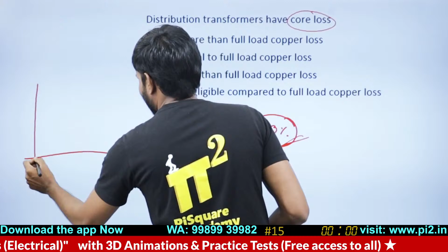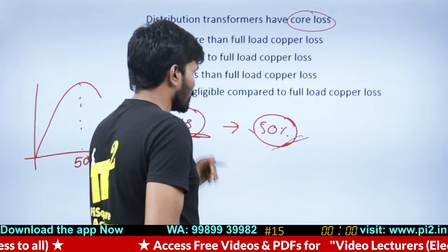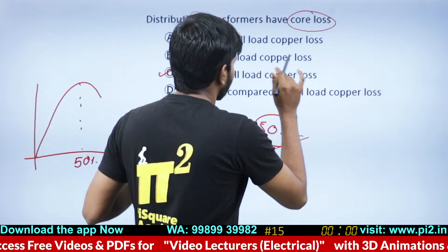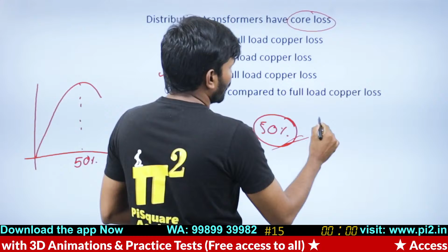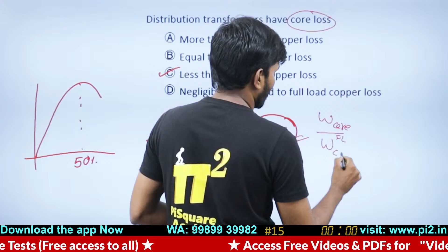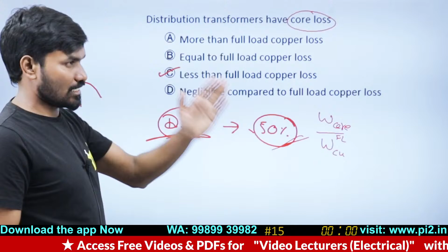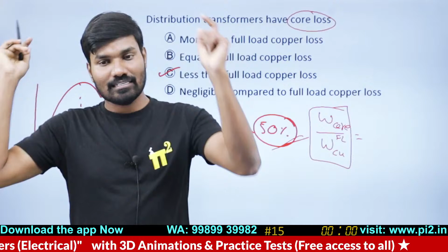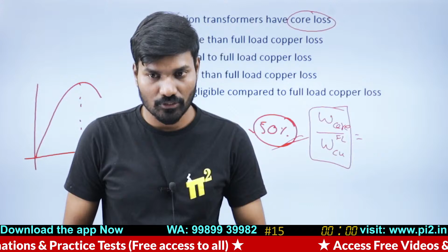Why? Because it operates at full load rarely, so your objective is to minimize the core losses, so that you ensure maximum efficiency comes somewhere around 50%, or maybe 60% or 70%. Within this range you get maximum efficiency for a distribution transformer, so you ensure core losses are much less than full load losses. Now tell me guys, if this has to happen, what's the ratio of core losses to copper losses, or full load copper losses to be more precise? If it has to be at 50%, I want efficiency to be maximum at 50%. Tell me, what should the ratio of core losses to full load copper losses be, so that efficiency will be maximum at 50%? That's a task for all of you guys, give your answer in the comments. Let's see how many of you answer it correctly.